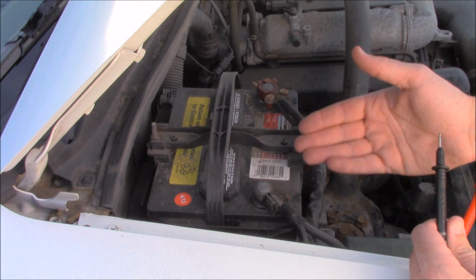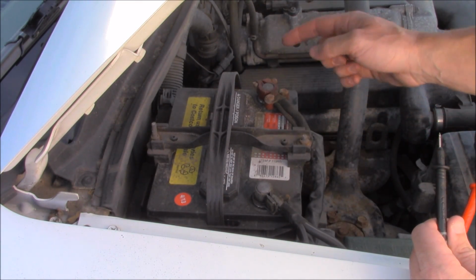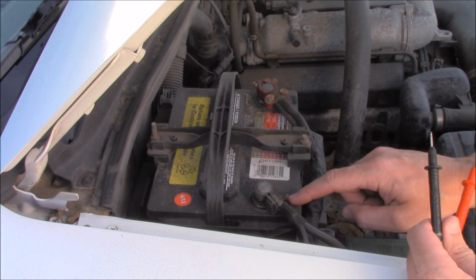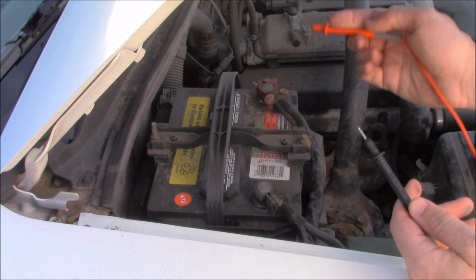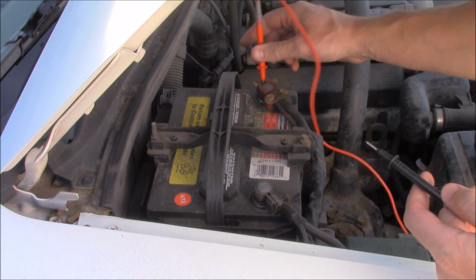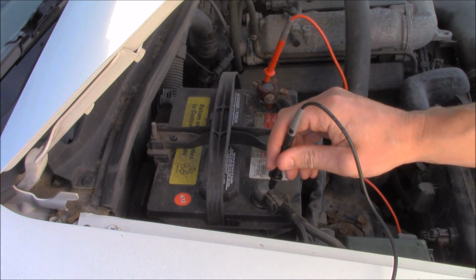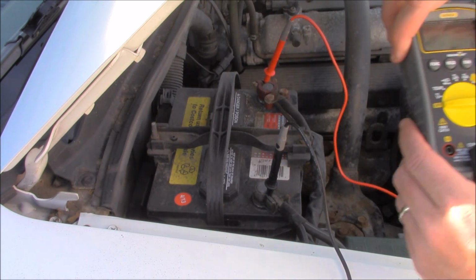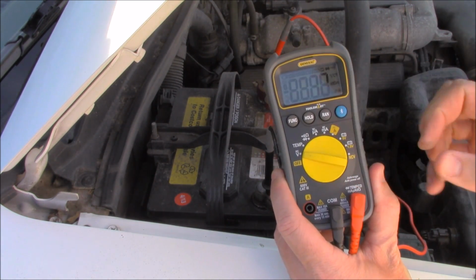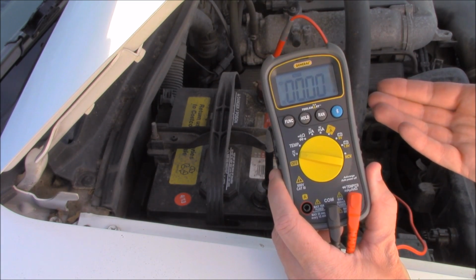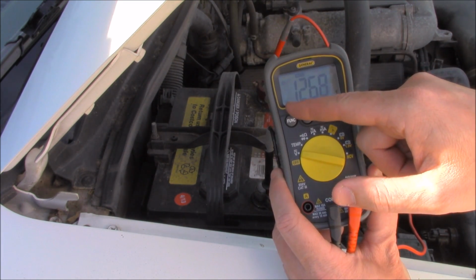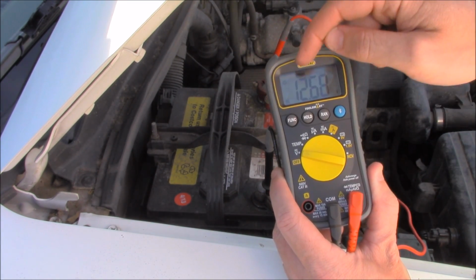On the top of the battery you'll notice two different posts, one positive terminal and one negative terminal. We'll take our red lead and place that on the positive terminal, and the black lead on the negative terminal. Now we can turn the unit on. This will automatically detect the voltage, and in this case it's DC voltage, with the battery reading a total of 12.68 volts.